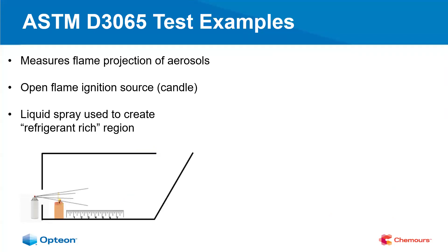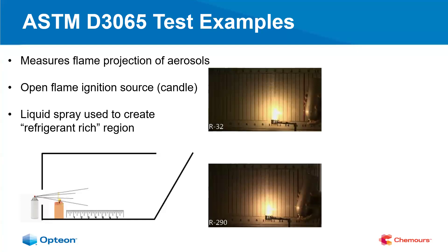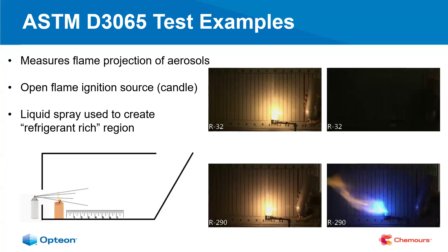Another test is the ASTM D3065 flame projection test, which measures the hazards of aerosol products. We invert a cylinder of refrigerant, spraying out a liquid-rich region across an open flame source — in this case a candle — to see what happens. With R-32 on top and propane on the bottom: every time we tested an A2L refrigerant, we extinguished the candle, primarily because you're not forming a flammable concentration at the candle and the pressure propelling the refrigerant forward actually extinguishes it. However, with propane, you could essentially create a blowtorch every time — propane is after all a soldering gas.